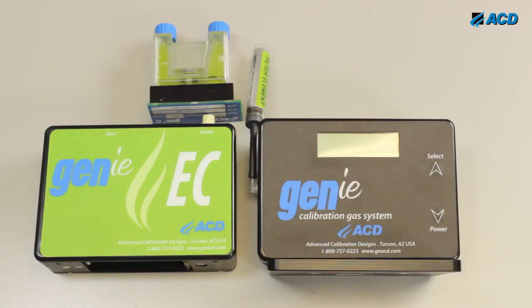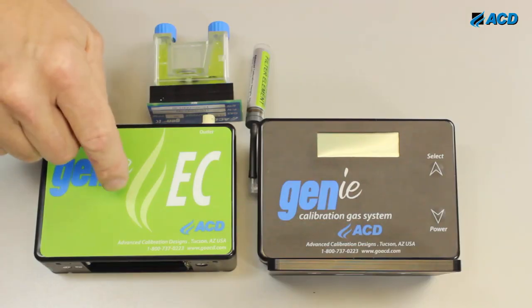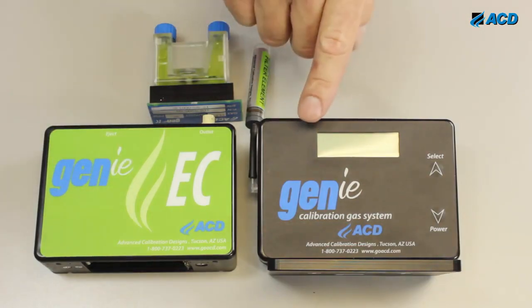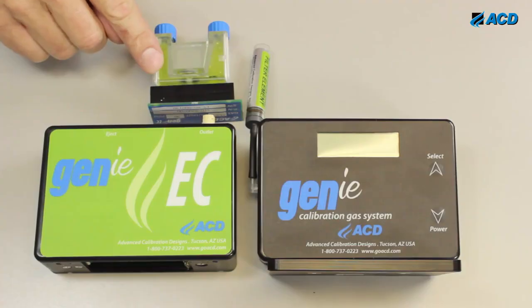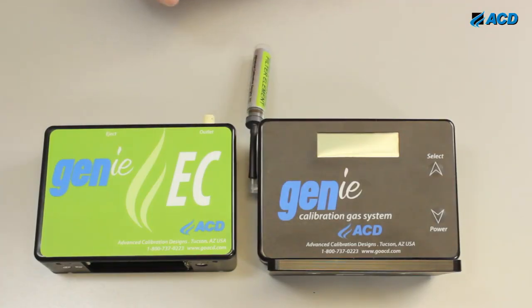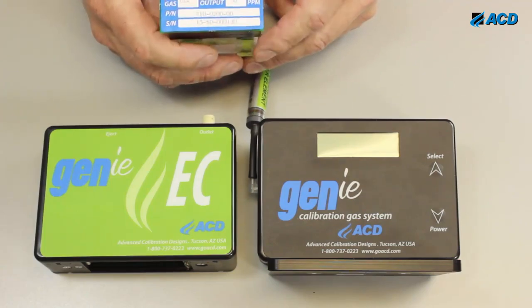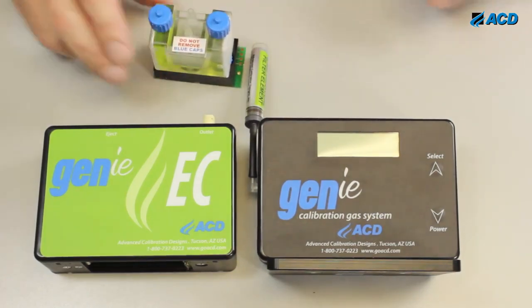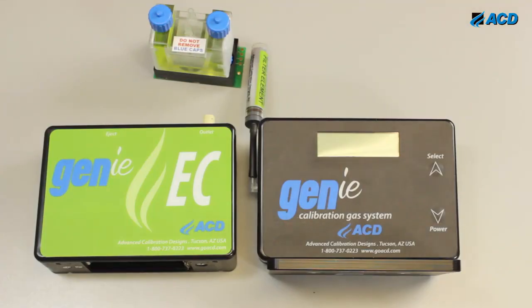The GENie EC calibration gas system is composed of three parts: the GENie EC module, the base unit, and a generating source. In this case, we have a chlorine gas generating source. Its range is 0.5 to 50 parts per million. When you order one of these units, it comes to you completely assembled and ready to go.